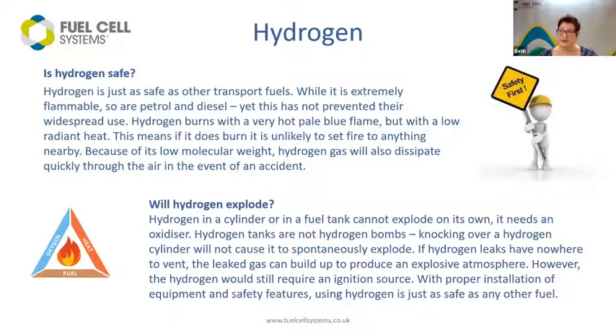Appreciate hydrogen for what it can do for us today. The key thing about hydrogen is it's the universe's smallest, lightest molecule. Given half a chance, all of it is going upward at 45 miles an hour, and not an awful lot can stop it. It's not even a greenhouse gas by the time it gets to the outside of the earth's stratosphere — it just gets whisked away by solar winds. You can use that buoyancy as part of your safety strategy, which is useful. Yes, of course it's flammable — all fuels are flammable — but it doesn't automatically explode just because it's exposed to the air. You need a specific reaction to get hydrogen to ignite. You need your fuel, your oxygen, and a spark all in the same place at the same time.